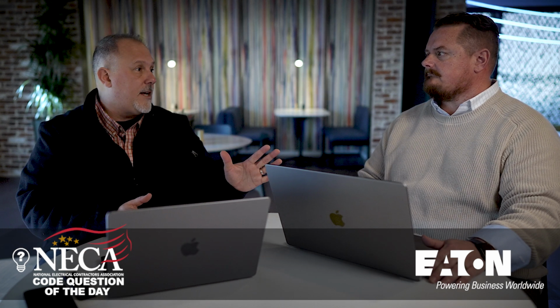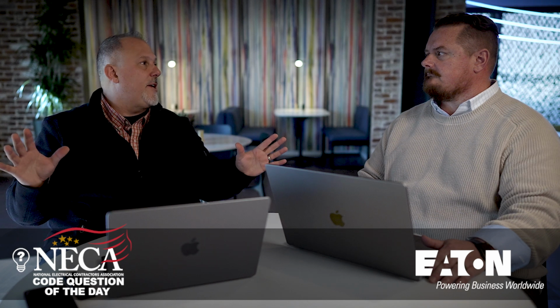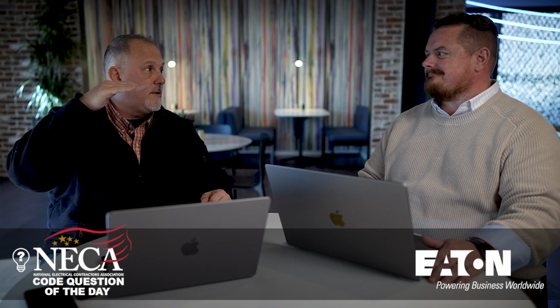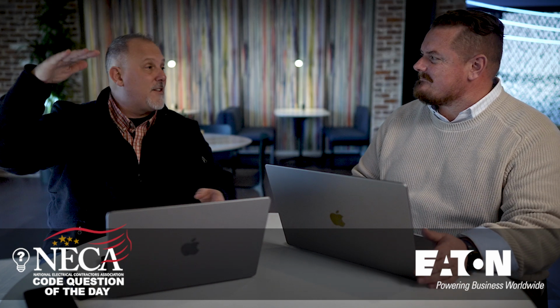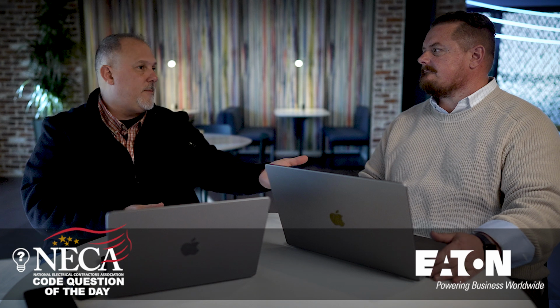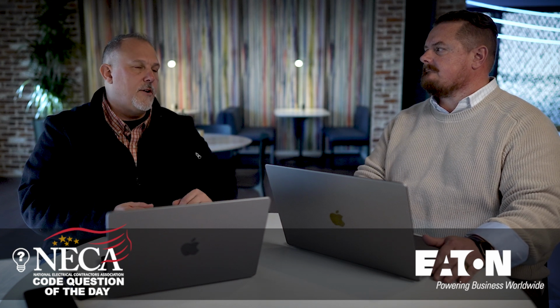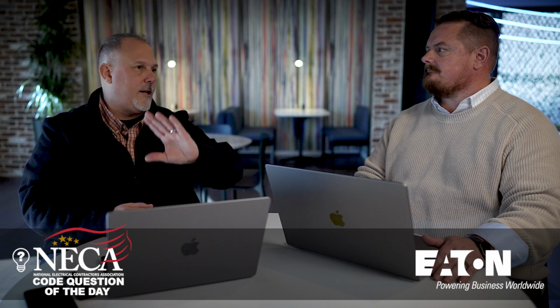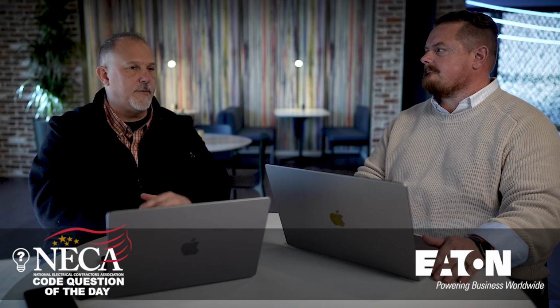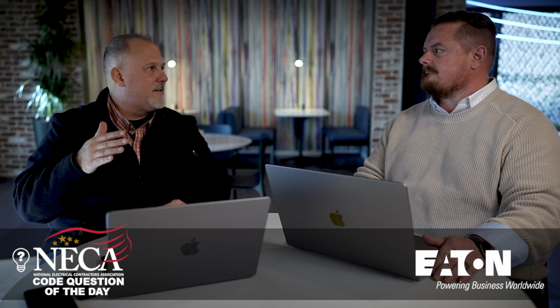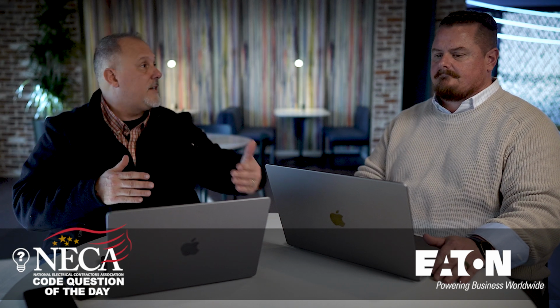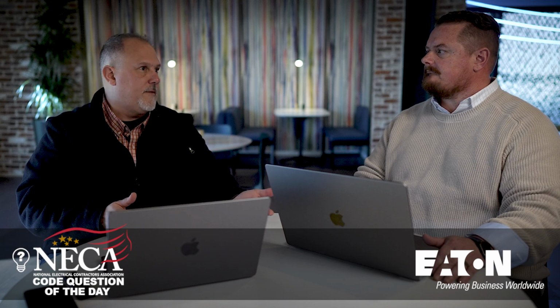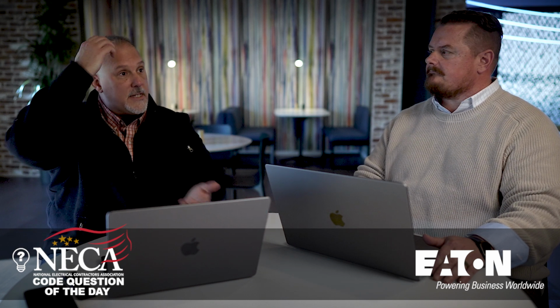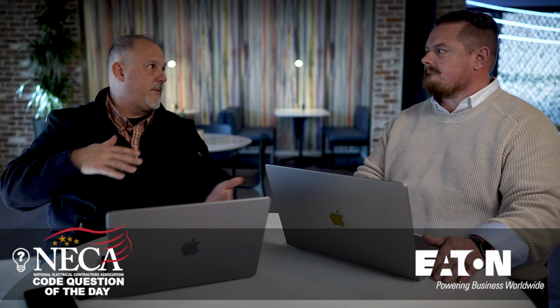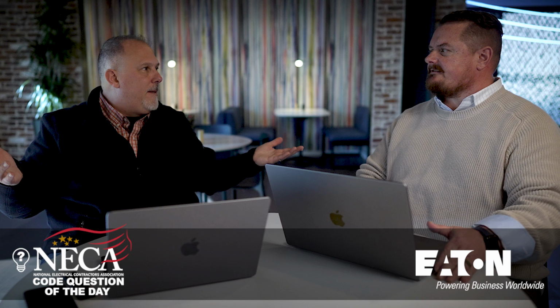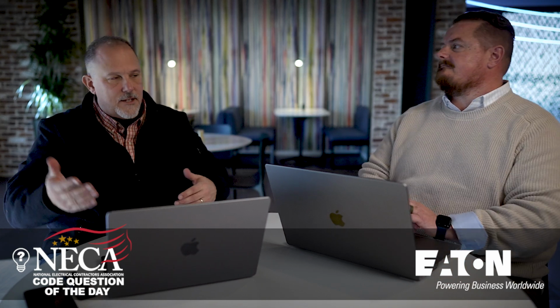So arguably I could say, when we say, well, I didn't have enough information. Well, you got to a point, and in many cases, you don't have to go all the way down to the equipment. Because if my equipment is 10K, I buy a panel board and it's the lowest short circuit current rating and interrupting rating of overcurrent devices, say 10,000 amps. Well, I only have to calculate as far down as just below 10,000 amps because any length of conductor I put down closer to that panel board, I know the fault current is going to be much less. So in many cases on the secondary of a transformer, I stop at the secondary of a transformer because when I get there, it should be less than 10K. It's going to be less, as long as, it depends on the size of the transformer and the impedance, whatnot.